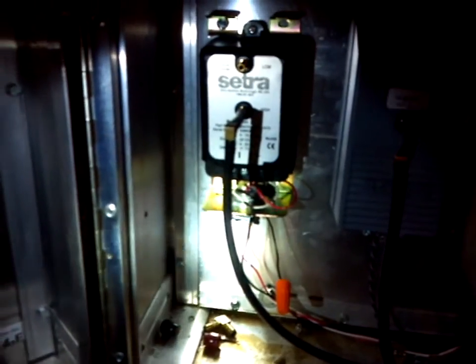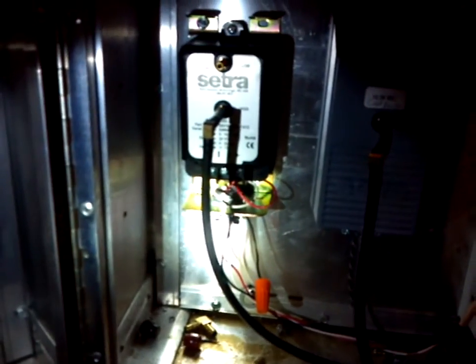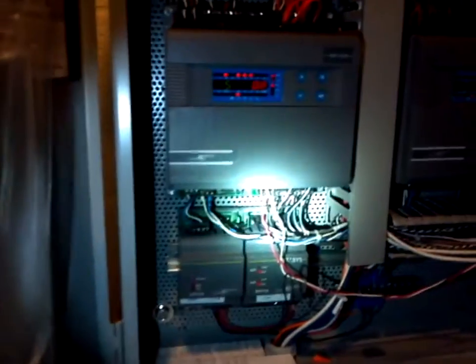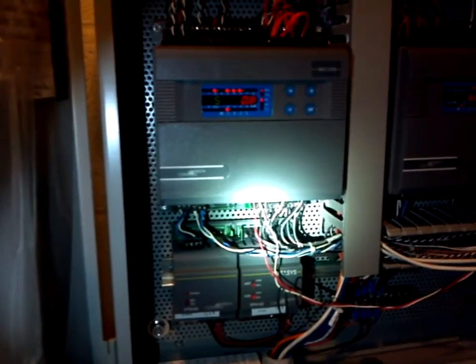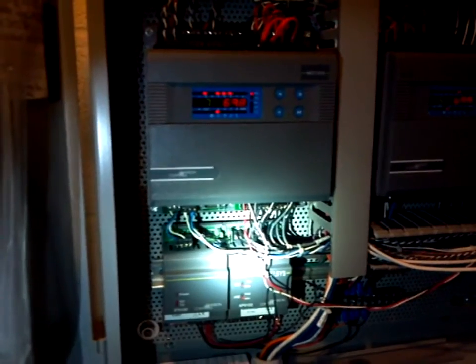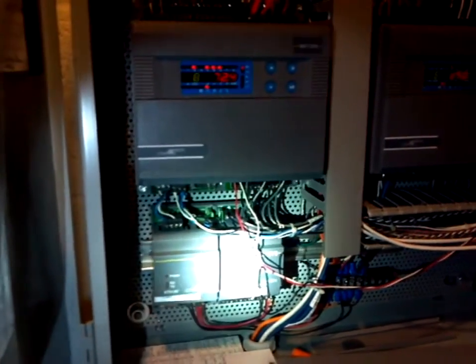That output, which is these two terminals here, which you can see from the one that is currently installed on our unit — the output from the Setra, whether it is a 0 to 10 or a 4 to 20, is tied to the input of our DX controller. This allows us to control the air handler VFD based upon the static pressure.